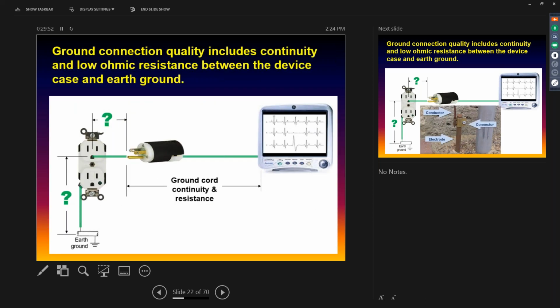What we've also been really diligent about, and it's a good thing, is being faithful to codes and standards on verifying continuity, the ohmic resistance between the case of our devices and the ground pin. Our safety analyzers measure all of this for us, and we want that resistance to be less than a half an ohm, 150 milliohms. We want it low, and that's what it should be since it's just a piece of wire. If we've got good mechanical contacts in the plug and on the case, that's generally not an issue.